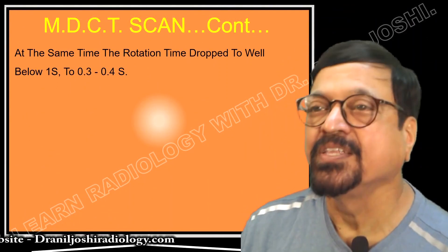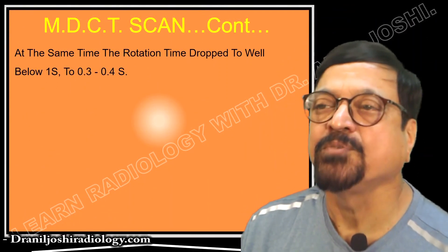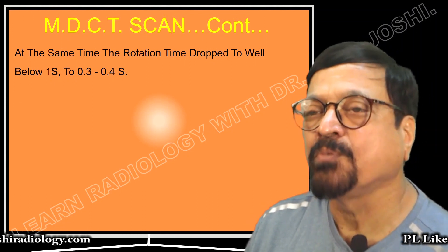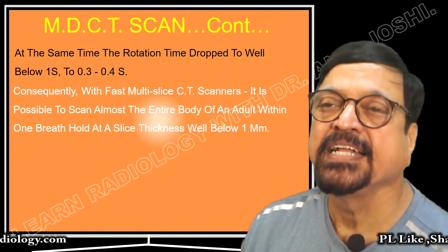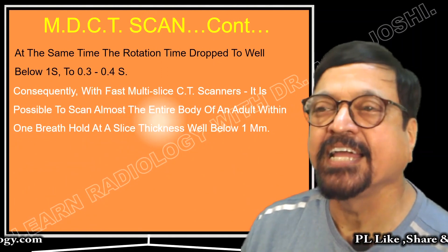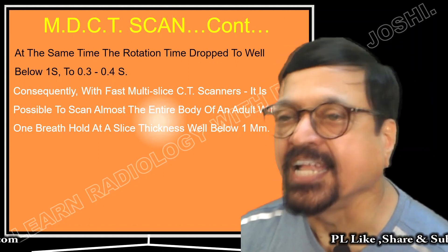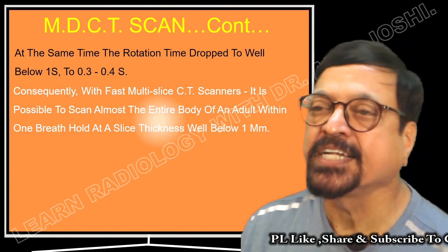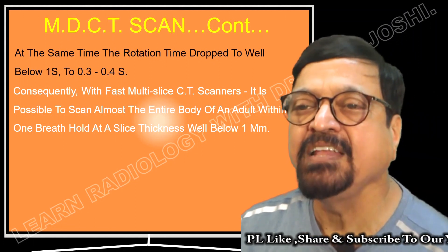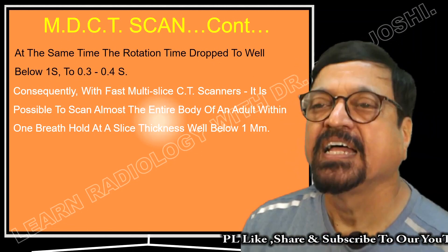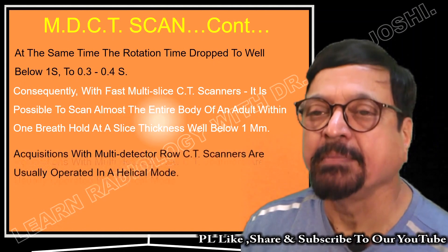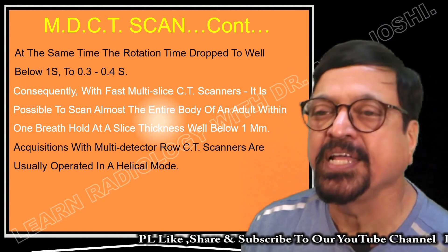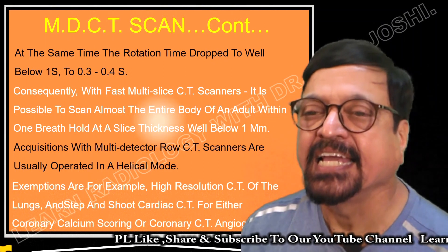At the same time, the rotation time dropped to well below 1 second, to 0.3 to 0.4 seconds — a fraction of a second per rotation. Subsequently, with fast multi-slice CT scanners it is possible to scan almost the entire adult body within one breath hold at a slice thickness of 1 mm. Acquisitions with multi-detector row CT scanners are usually operated in helical mode.